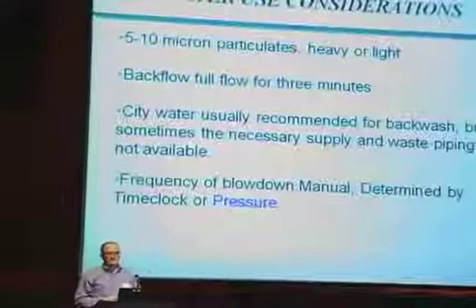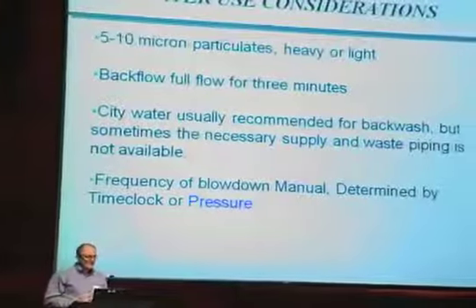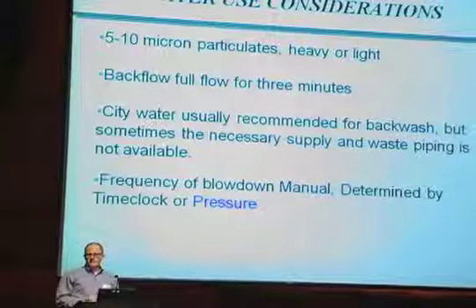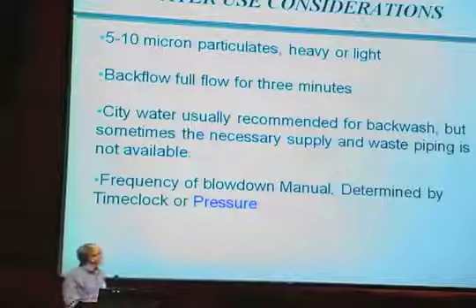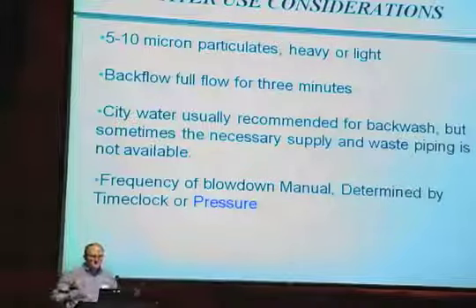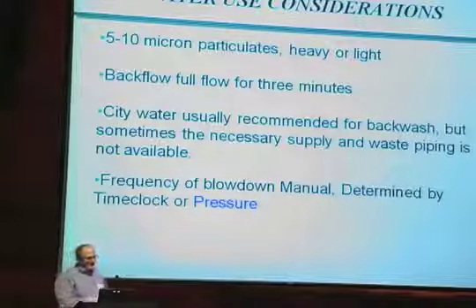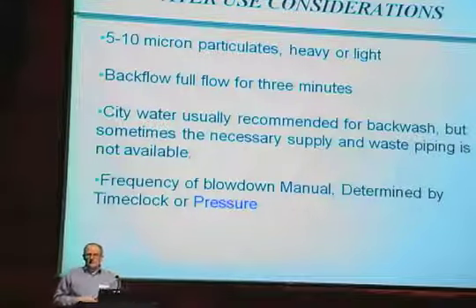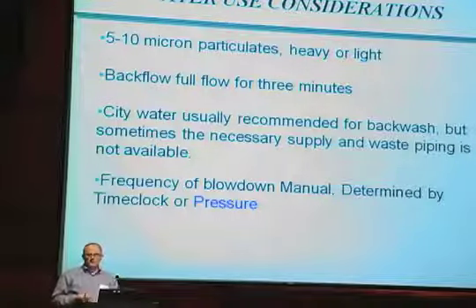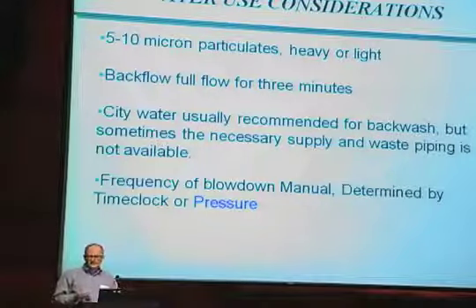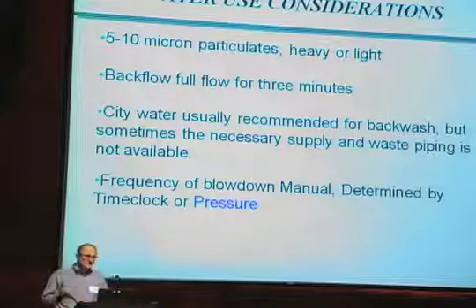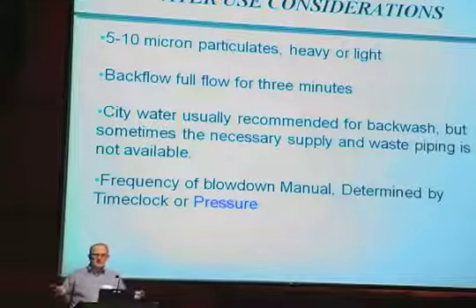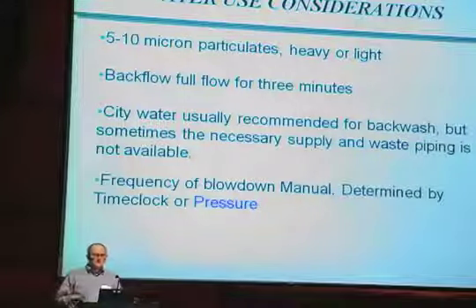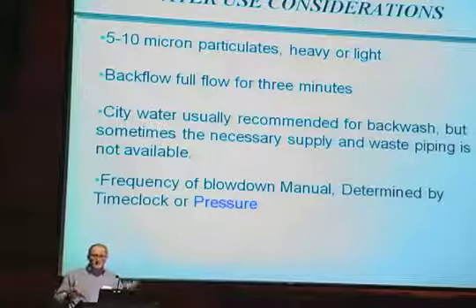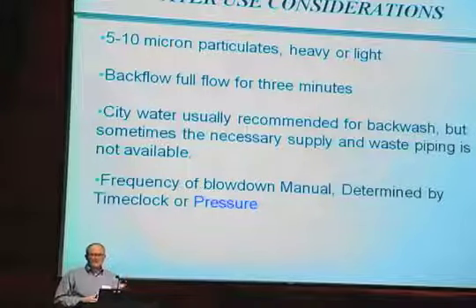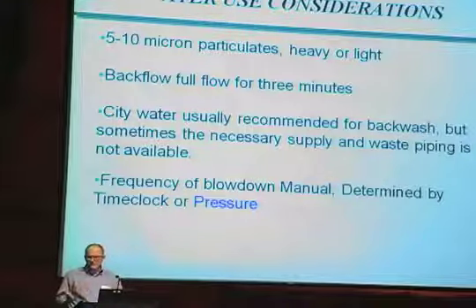The advantage of this type of system is, one, as I said, it's regenerable, but also it is probably one of the most efficient regenerable processes. You can get to 5 to 10 microns, which is typically what you see on those. But they do have heavy water use because you need to backflow for a full 3 minutes. Now, generally, these things are in side stream operation, so let me put some numbers to that. If it's a 1,000 gallon per minute cooling system, which is about 330 tons plus or minus, you would generally run anywhere from 10 to 15% of the water through here.